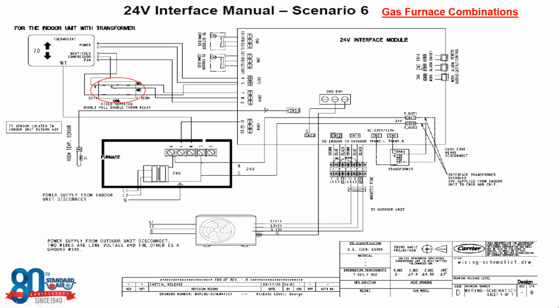Okay, the second change on here, of course, is going to be the fact that we're actually setting up this thermostat as a heat pump thermostat now, or a dual fuel thermostat. So you're still going to have your R and your C, so your hot and your common, coming from the thermostat, feeding into the 24 volt interface. But now we're going to take that O terminal and we're going to feed it through the continuous duty coil one, which is going to feed back into the common.